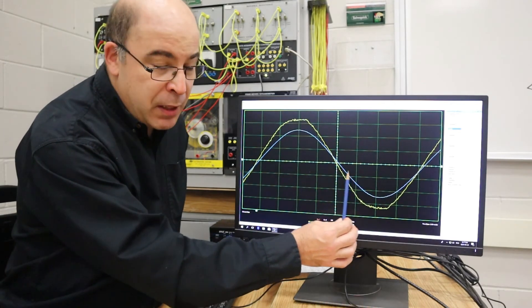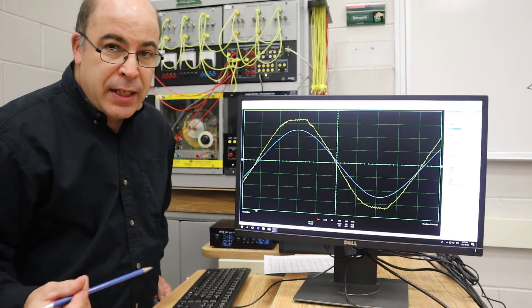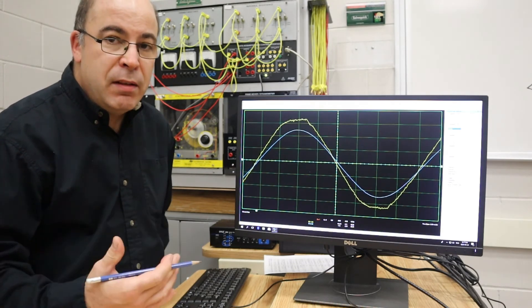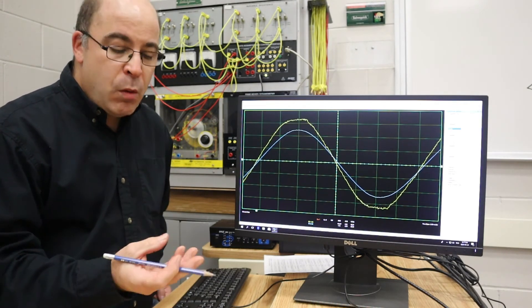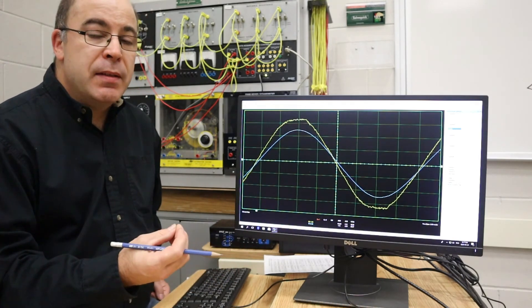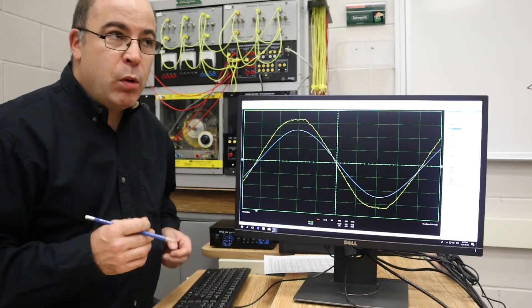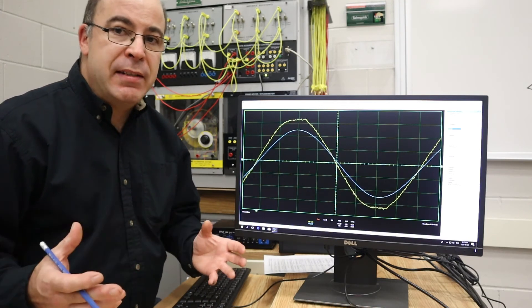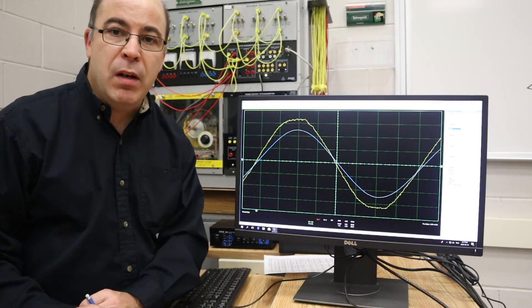When you have power that falls beyond this, you're actually inefficient, and the utility has to provide you with all the true power your equipment requires, plus all the reactive power, or what we would call the magnetizing current to make an electric motor run.